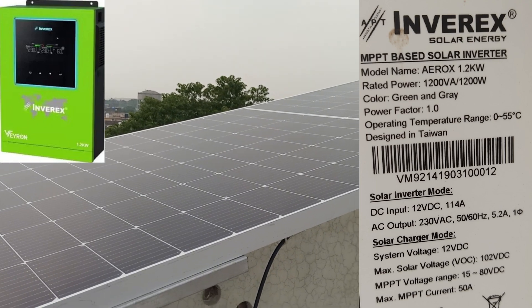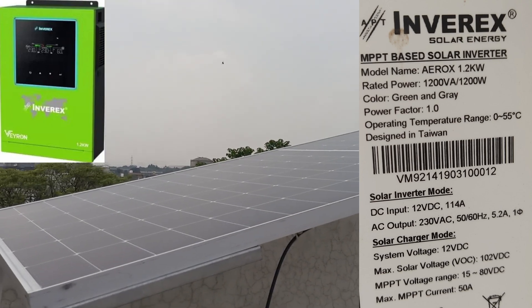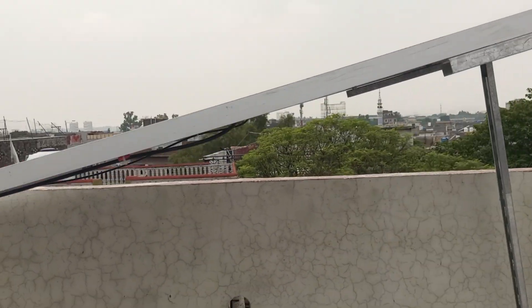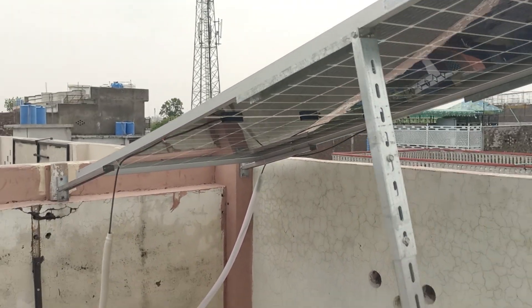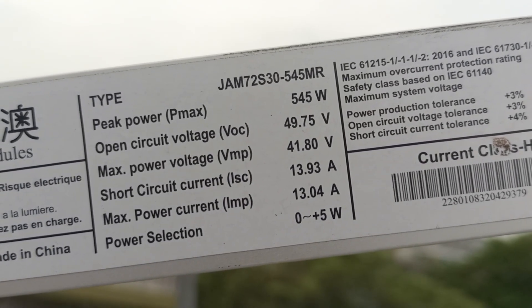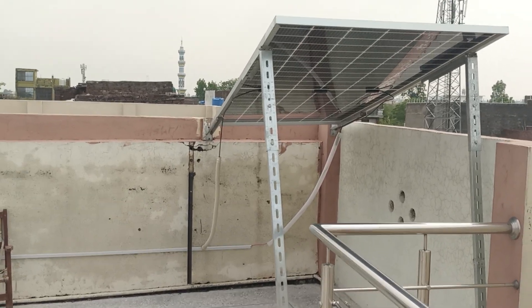The inverter we are using is the Inverex Veyron 1.2 kilowatt. It can take solar input voltages from 15 to 80 volts and current up to 50 ampere. Our solar panel is 50 volt and 14 ampere maximum current, so we can install one, two, or three 545 watt solar panels with this inverter.